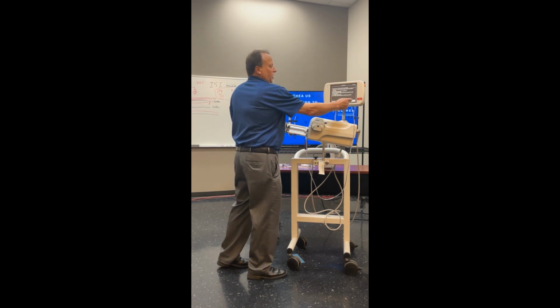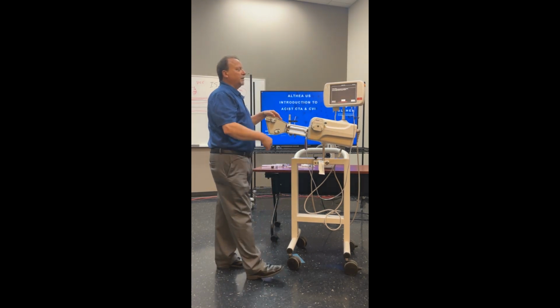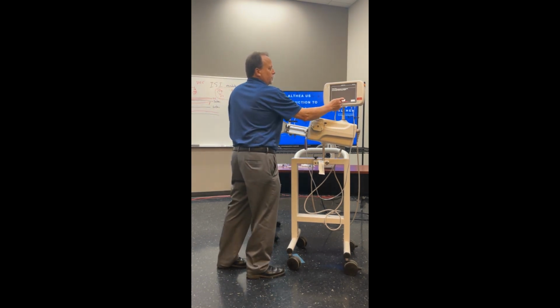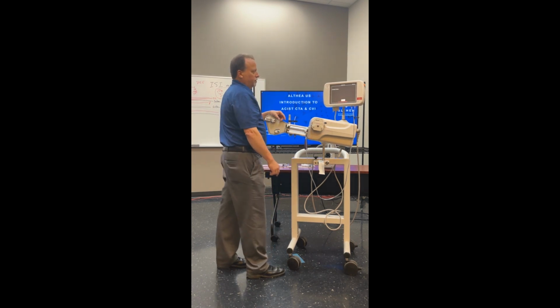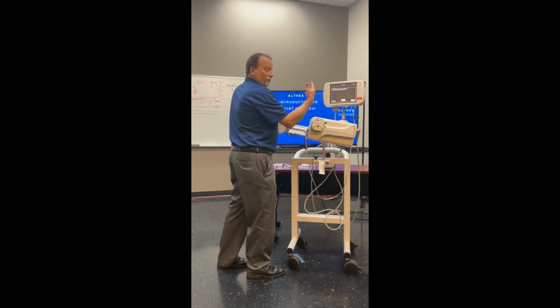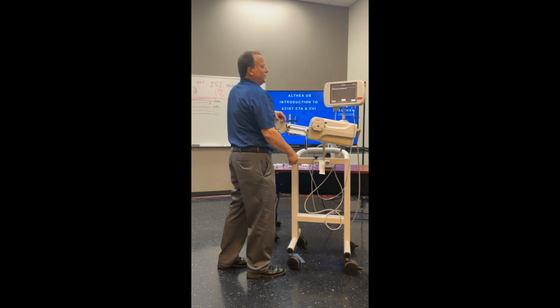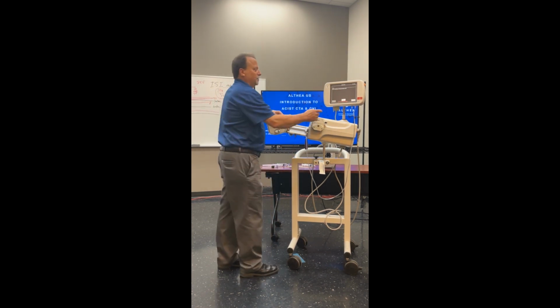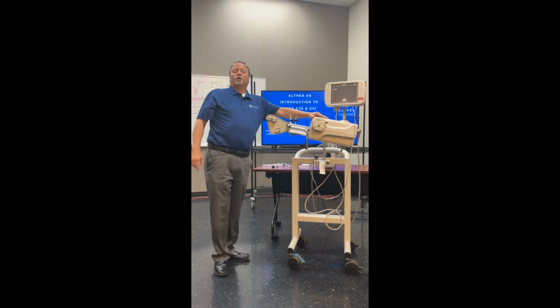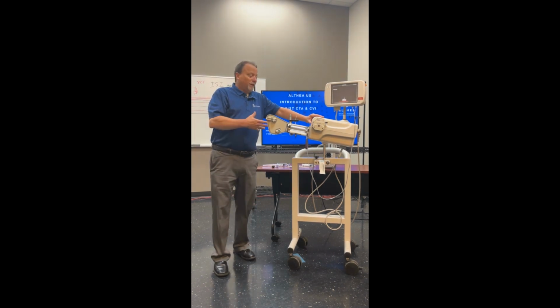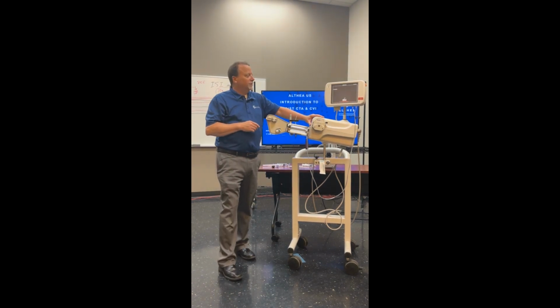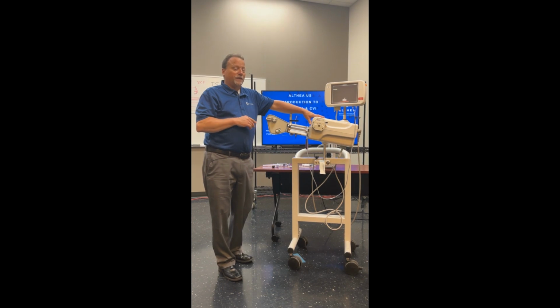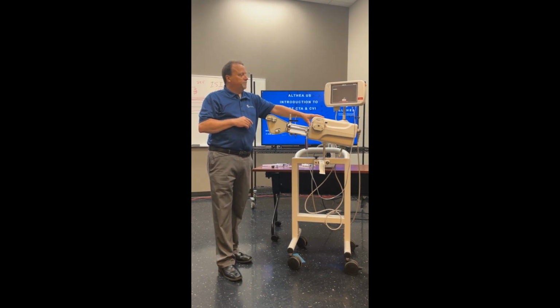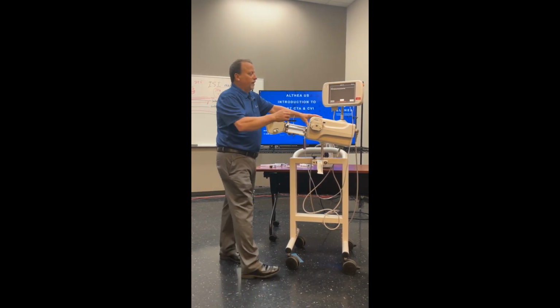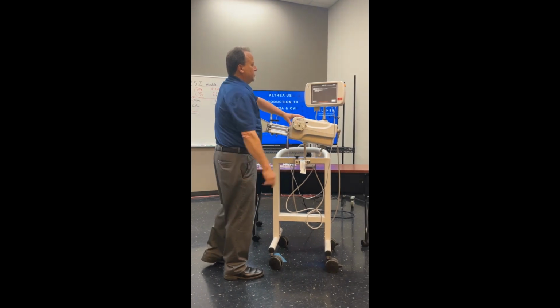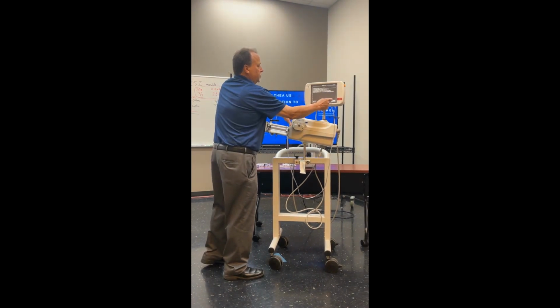It says to load saline. We don't worry about that. Purge tubing. We're going to purge it. We've done that. Hit done. Now we're going to hit flush. This is where you can check your pump to make sure it's not excessively noisy. It'll run automatically for 10 seconds. We've done that. We don't have to purge air again.